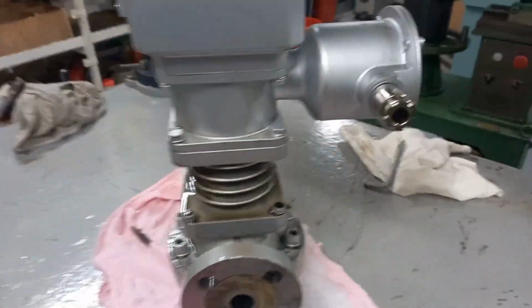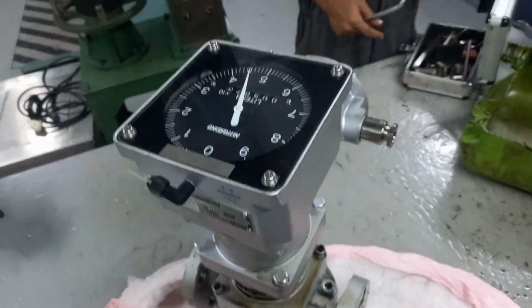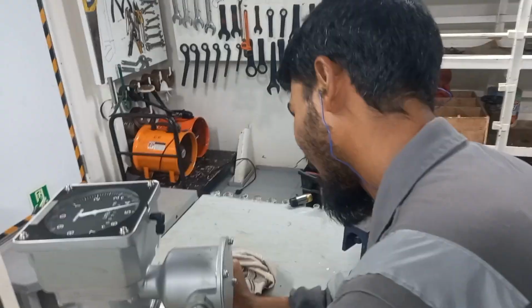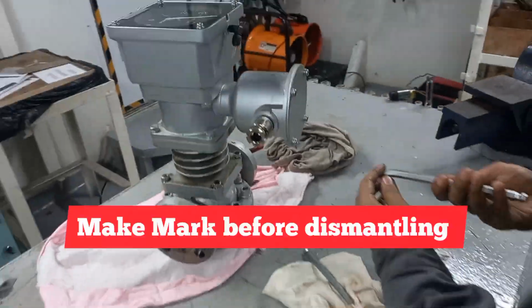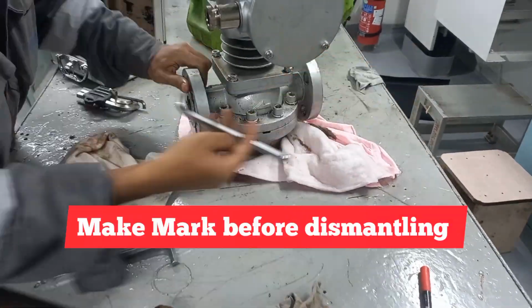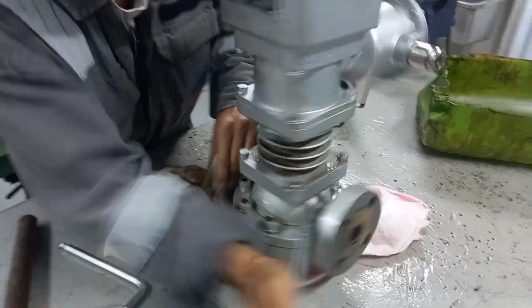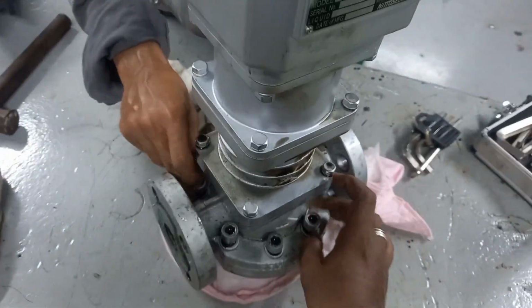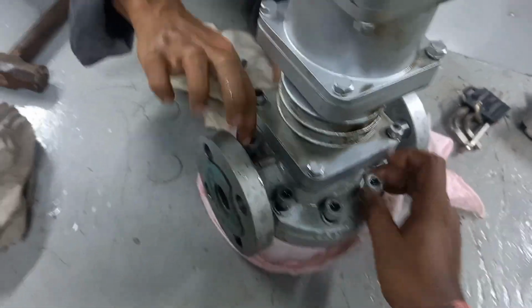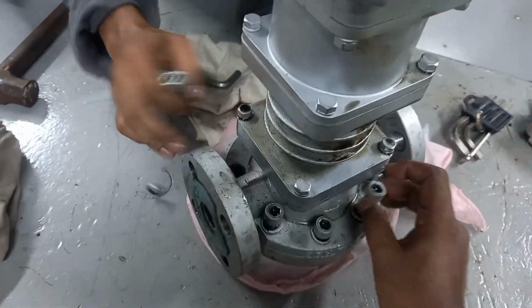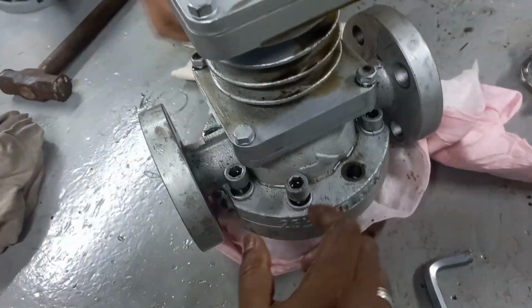A fuel oil flowmeter is an important measuring instrument installed on board ships to measure the volume or mass of fuel oil supplied to the main engine, auxiliary engines, and boilers. The most commonly used types on ships are mass flow meters, like the Coriolis type, and volumetric flow meters, like the oval gear type.